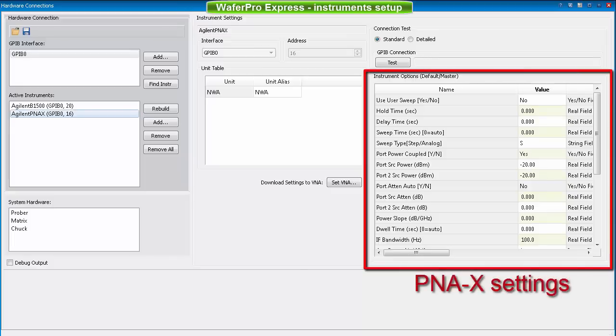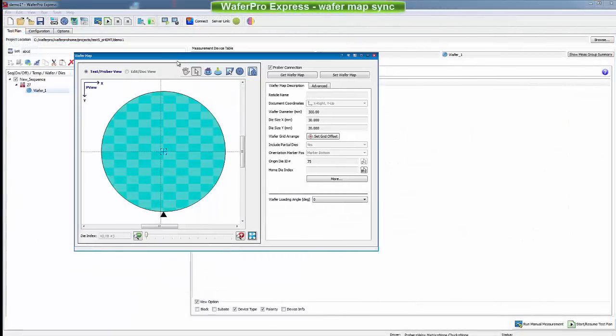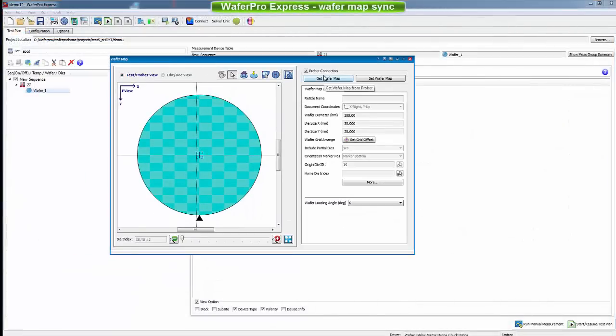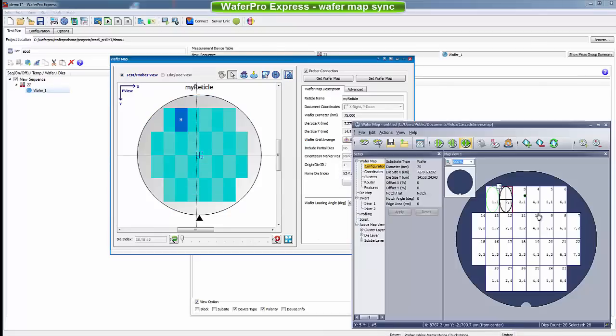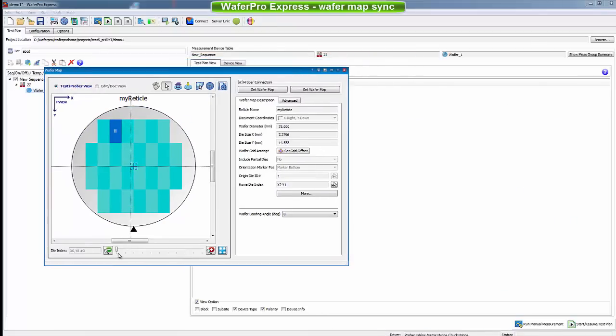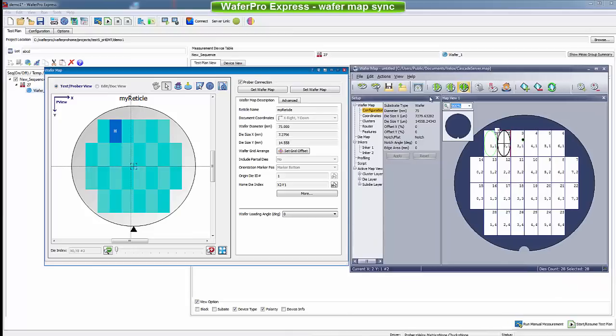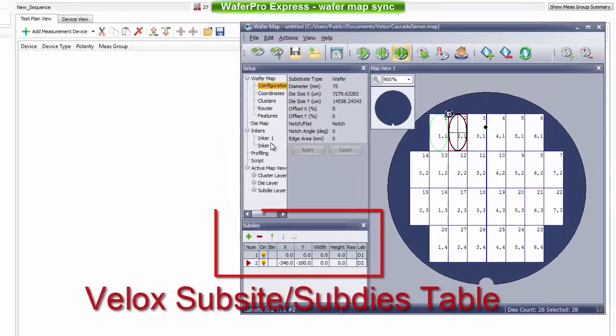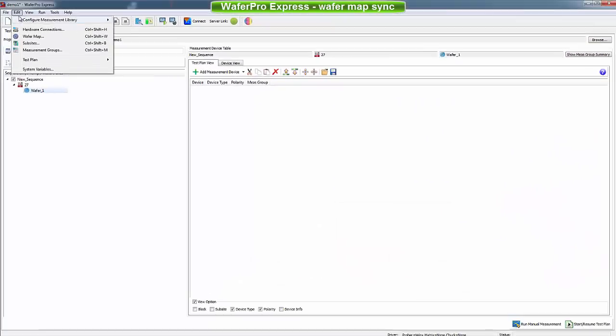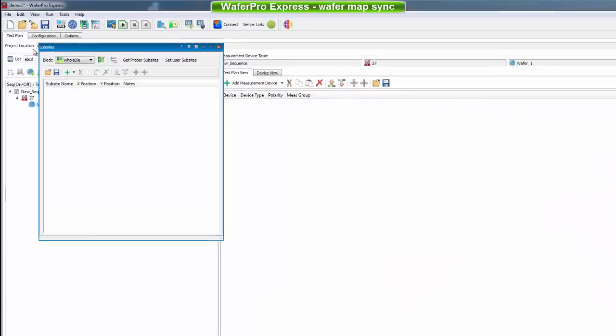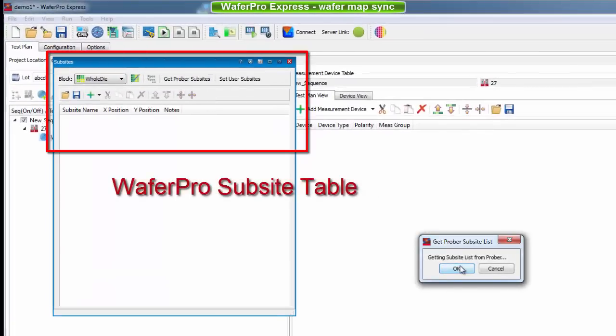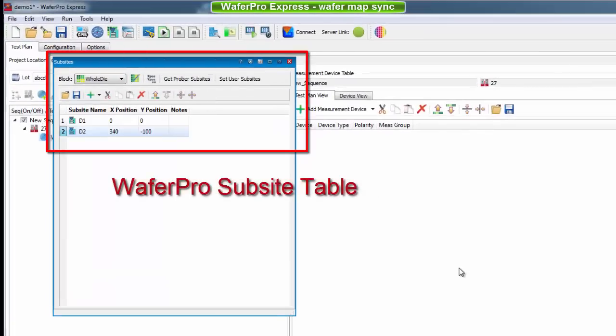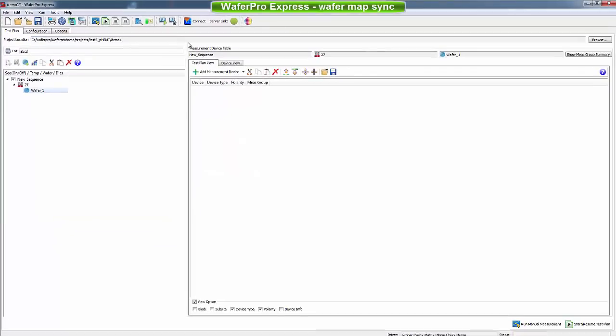The next step is to synchronize the wafer map. With one click, WaferPro reads the map information from Velox, including the home die location. The subsite table lists the names of all the subsite locations and their intradie coordinates. If desired, the subsite table can be read directly from Velox or loaded from file. Velox and WaferPro are now fully synchronized and ready for real measurement action.